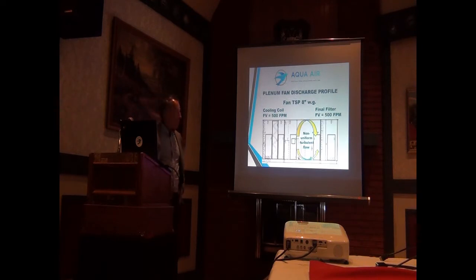Plenum fans, great improvement, works on pressurization. When you talk about the fan discharge profile of this fan, as you can see, the orientation of the fan is a bit different, still on the base with the spring isolation, belt driven, so you still got the belt drive losses.